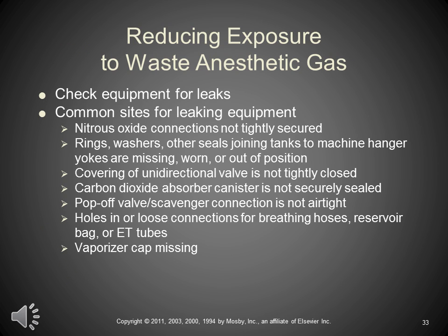There are a lot of simple things that can be done to reduce the exposure to waste anesthetic gases. Check the equipment for leaks. If it's leaking, yeah, you're going to get exposure. If it's not leaking, you're probably not. Common sites for leaking equipment: the nitrous oxide connectors are not securely tightened. Rings, washers, seals joining tanks to machine, hanger yokes are worn, missing, lost, non-functional, covered with mold, who knows.